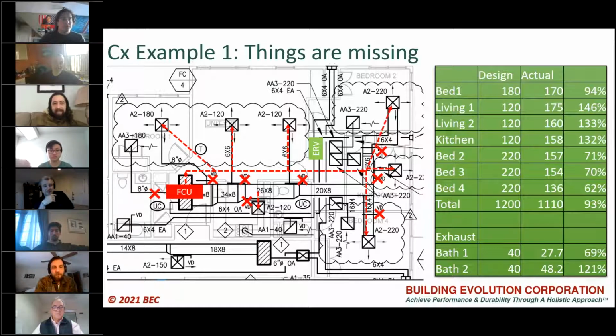I was talking with the owner about this. Even if you went back and retrofitted these things, do you want to have 7, 8, 9 access panels inside your living room on each apartment? Probably not. So there's other ways of doing it, such as restricting it at the actual diffuser, putting in a car damper in line with the duct at the diffuser. That way you don't have to actually damage your ceiling and pull the whole thing down or put in access panels everywhere. It's a good retrofit solution, but also if we were on this, we probably would have recommended it as a design solution.